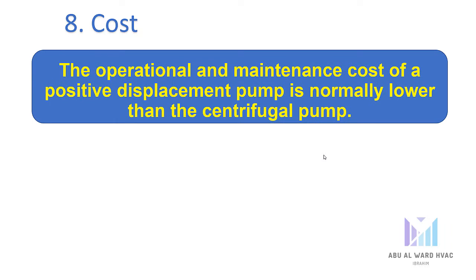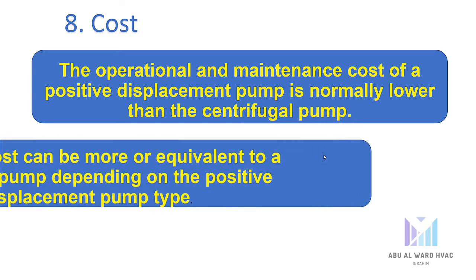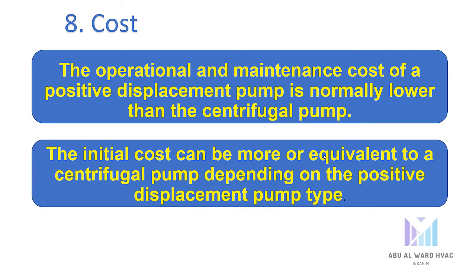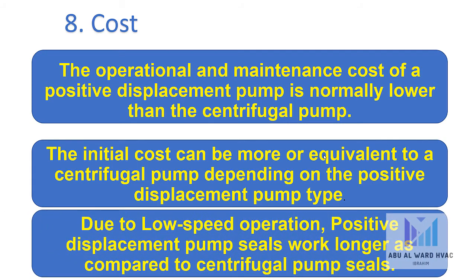The eighth aspect is cost. The operational and maintenance cost of a positive displacement pump is normally lower than that of a centrifugal pump. The initial cost can be more or equivalent to the centrifugal pump depending on the positive displacement pump type. Due to low-speed operation, positive displacement pump seals last longer compared to centrifugal pump seals.